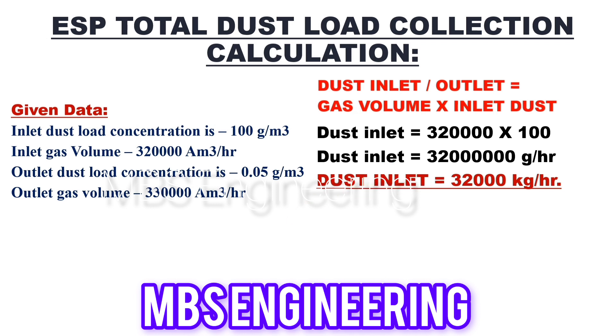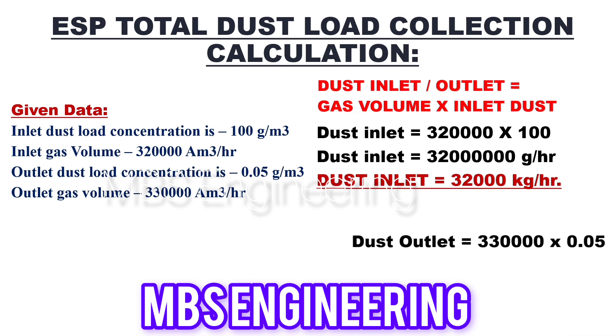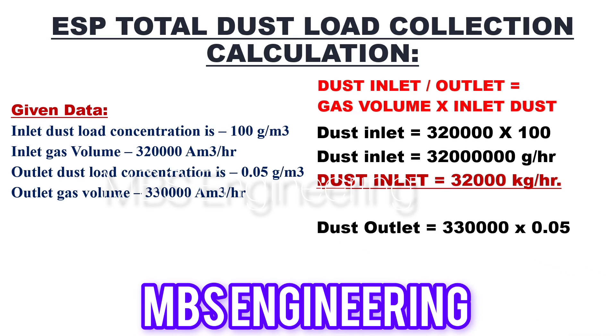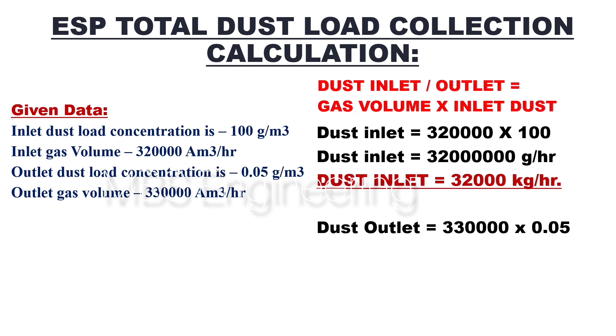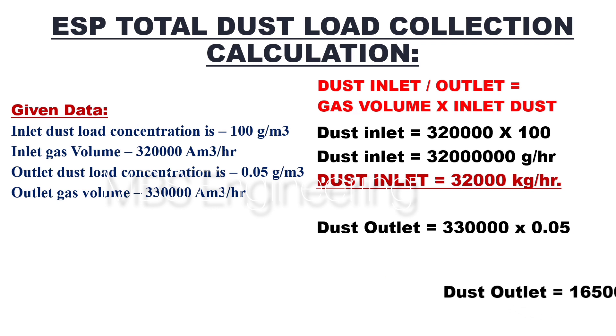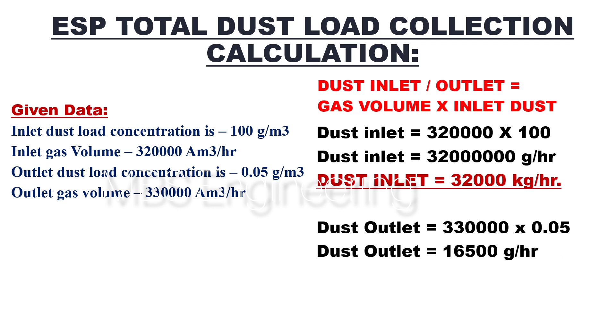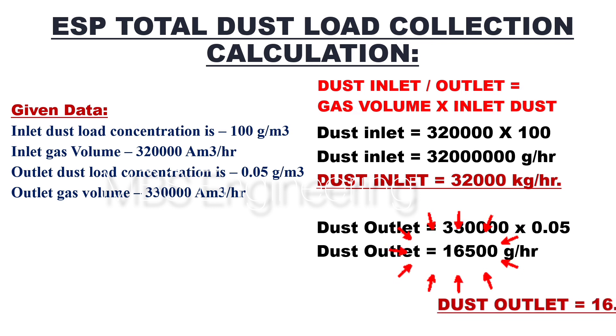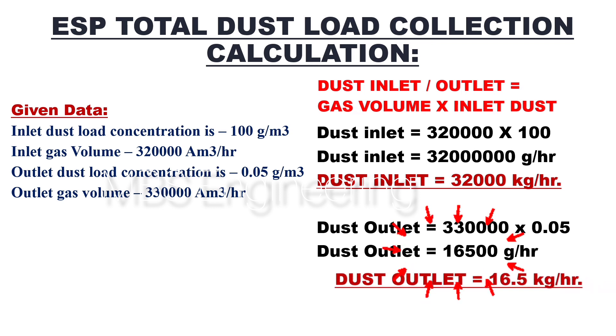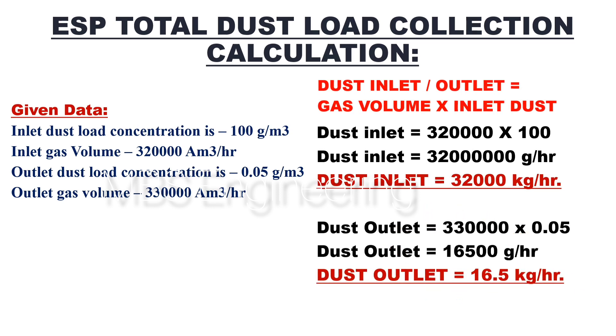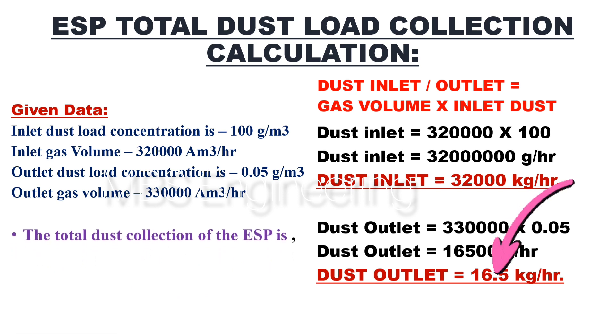Gas outlet dust concentration equals 3,30,000 multiplied by 0.05. The dust outlet concentration is 16,500 grams per hour. To convert into kilograms per hour, 16,500 is divided by 1,000. The obtained outlet dust concentration value is 16.5 kilograms per hour.